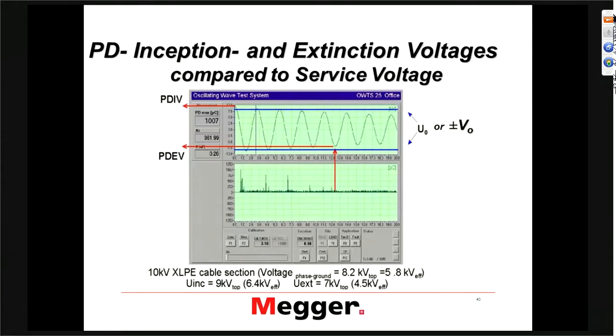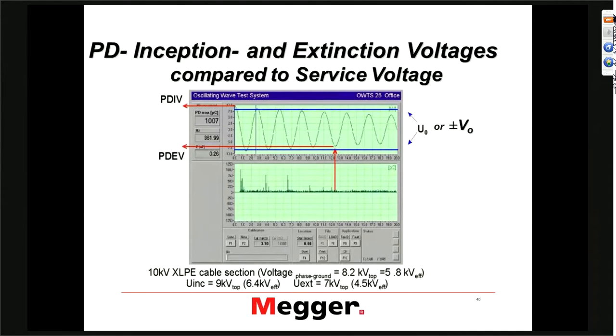When you do PD testing, you always want to test at a somewhat higher voltage than operating voltage — to simulate maybe a switching surge — and to see whether a switching surge could create PD that would persist at lower than operating voltage levels. For the most part, we recommend 1.2 to 1.3 U-naught, which will normally be good enough to ensure your extinction level is still above operating voltage. This particular aspect of checking the cable for switching surges cannot be done when doing an online test, because you can never exceed your operating voltage.